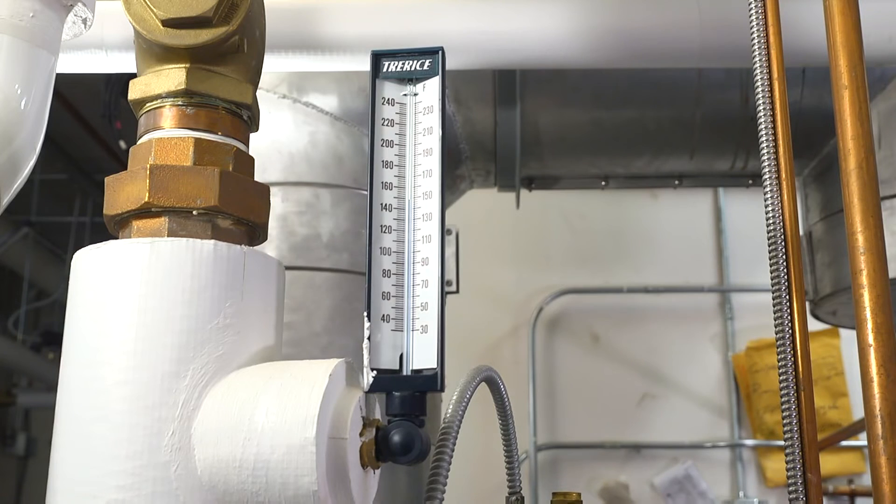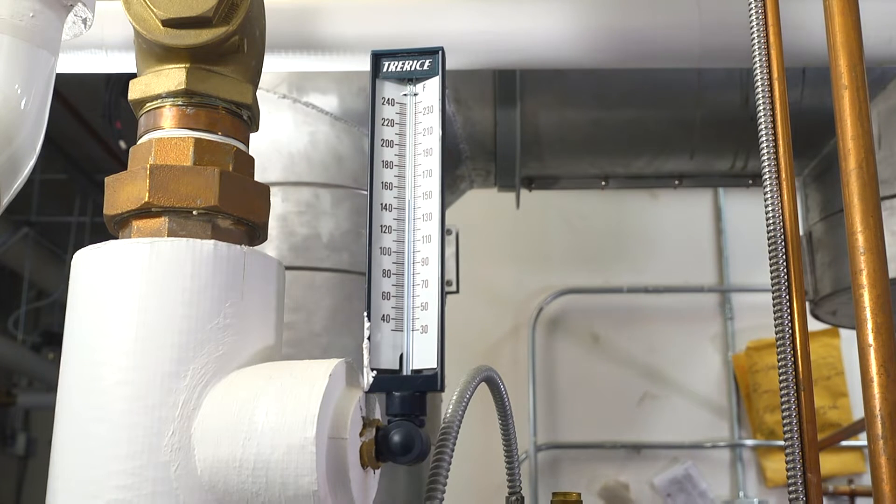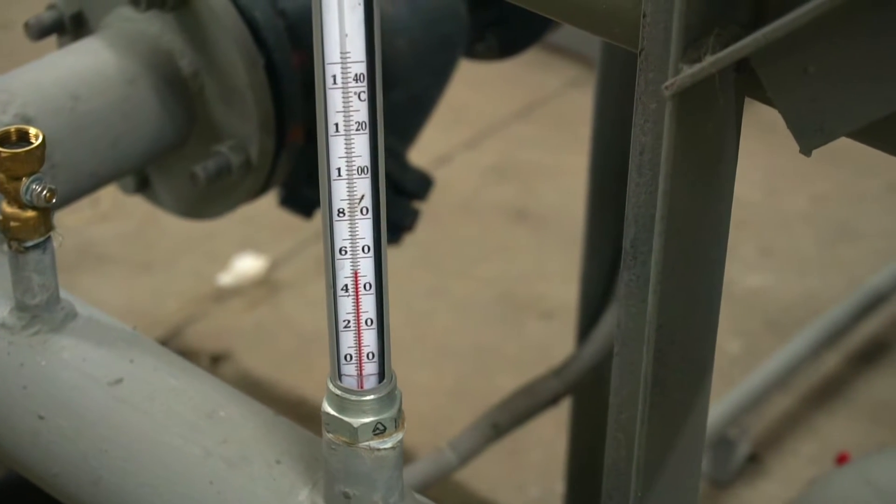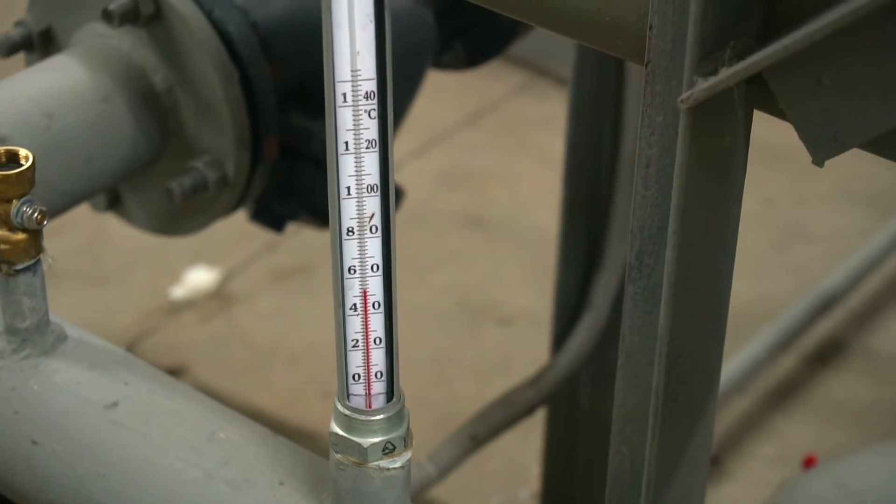Additionally, there's other sensors, like the sensors in the hot water system that the boilers are controlling to. You can use local gauges, thermometers, pressure gauges to compare sensor readings on the building automation system to what you're seeing in the field.